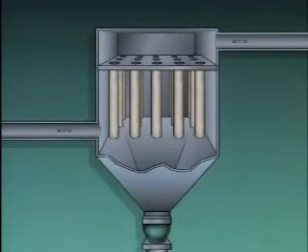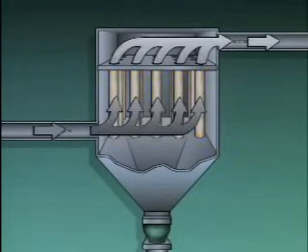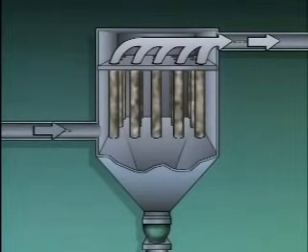A bag house, on the other hand, uses a series of porous bags installed in the gas flow path to physically filter particulates from the combustion gases. As the combustion gases are drawn through the bag house, particulates are trapped on the surfaces of the bags while the rest of the combustion gases pass through.